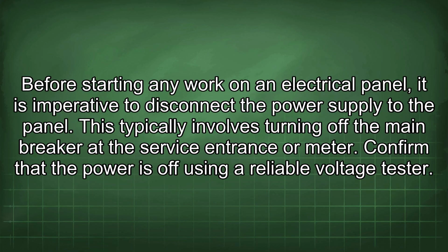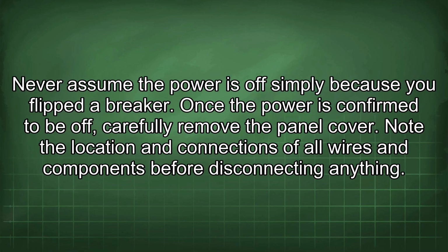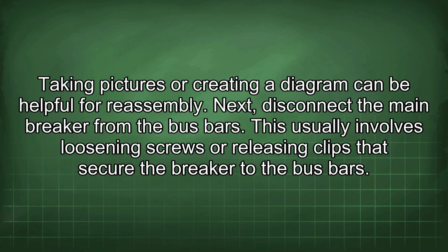Before starting any work on an electrical panel, it is imperative to disconnect the power supply to the panel. This typically involves turning off the main breaker at the service entrance or meter. Confirm that the power is off using a reliable voltage tester. Never assume the power is off simply because you flipped a breaker. Once the power is confirmed to be off, carefully remove the panel cover. Note the location and connections of all wires and components before disconnecting anything. Taking pictures or creating a diagram can be helpful for reassembly.